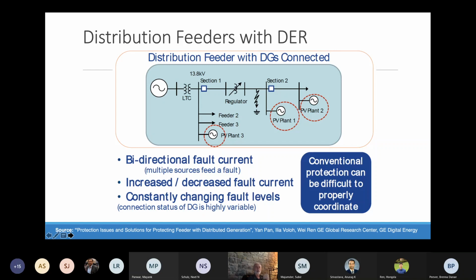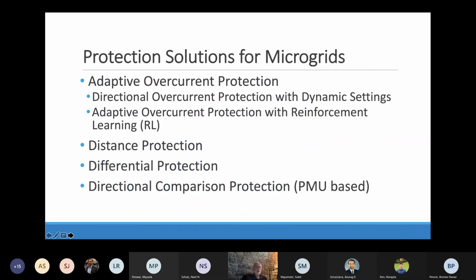Load is changing all the time, and so does the PV production. So the levels of the fault currents and directions that the fault location represented in the middle of that picture is attracting current into itself can be multiple. Those conditions change, and traditional time delayed overcurrent protection may be inadequate to capture all of those situations. So those circumstances have driven us to consider alternative solutions.